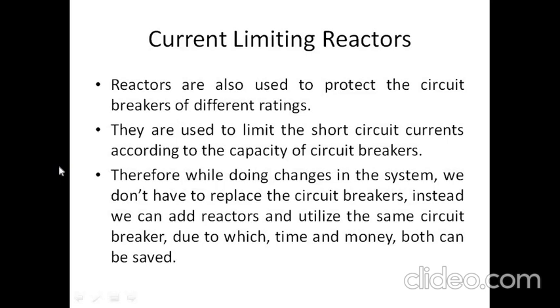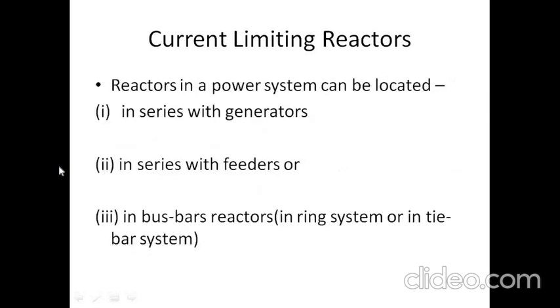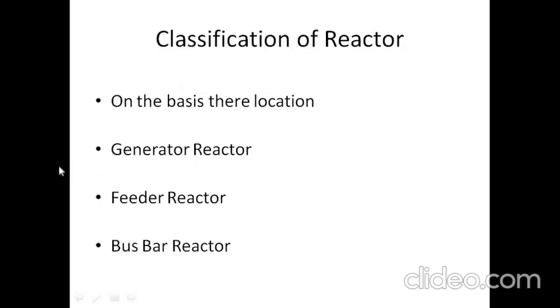We can utilize the same circuit breaker just by adding reactors in the system, saving both time and money for installation and maintenance. Reactors in the power system can be located in different positions: connected in series with the generator, in series with the feeder, or as bus bar reactors. According to their location, the type of reactor system is identified.